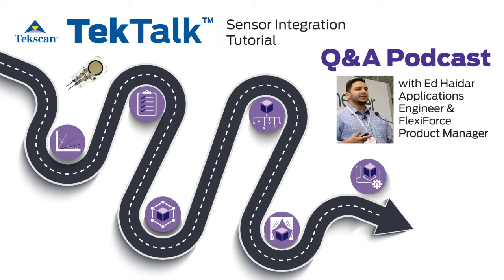Okay, thank you. This next person is asking about trimming the sensor. They know you can cut the FlexiForce sensor. The question is, can they trim it? They need a very small sensing area, and they are afraid that if they cut too much of the sensor, it will lose its performance. Sure. Yes, trimming the leads of the sensor, for example for our A201 series or our A401 series, is something we can absolutely do. We can make the leads shorter for you and pin them with our square male pin standard termination, so that you've got a shorter tail length.